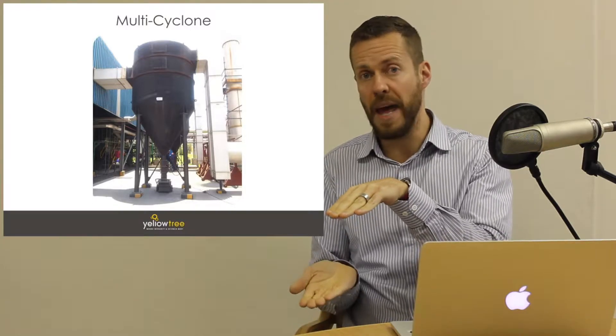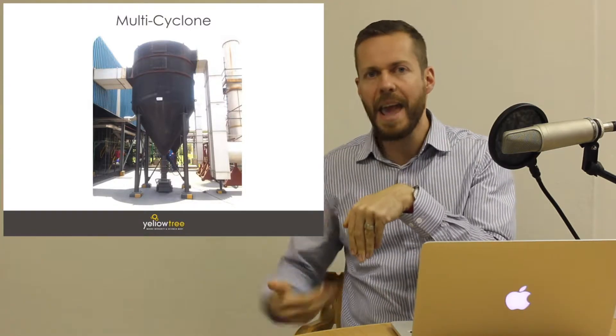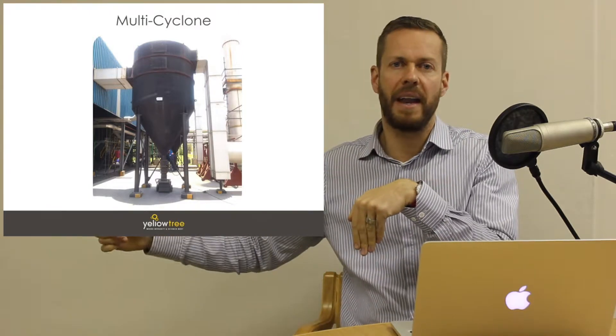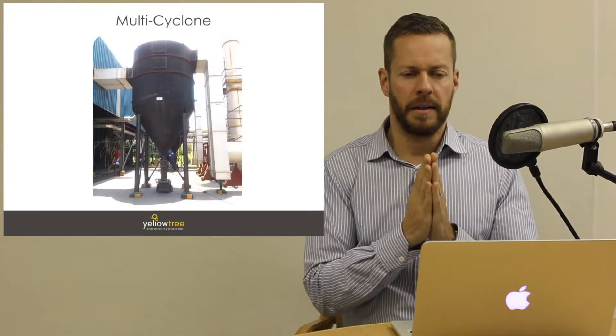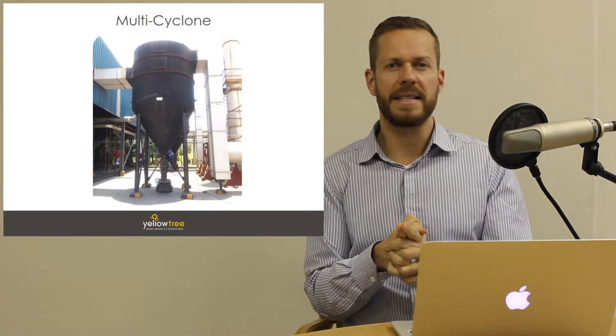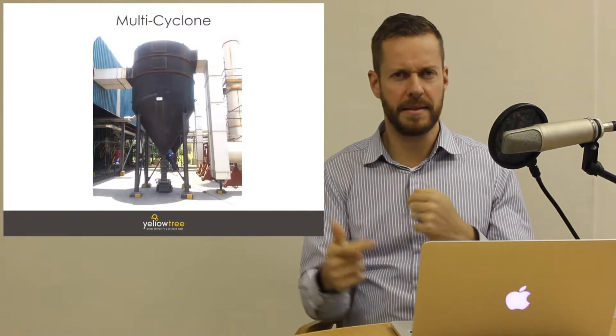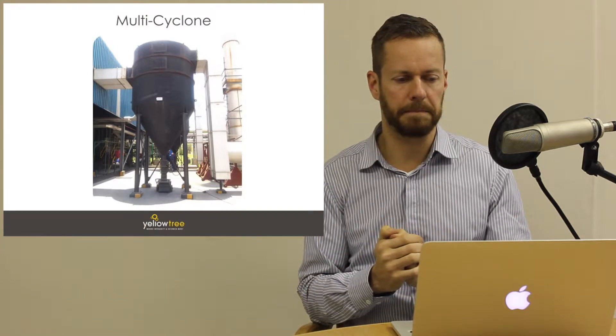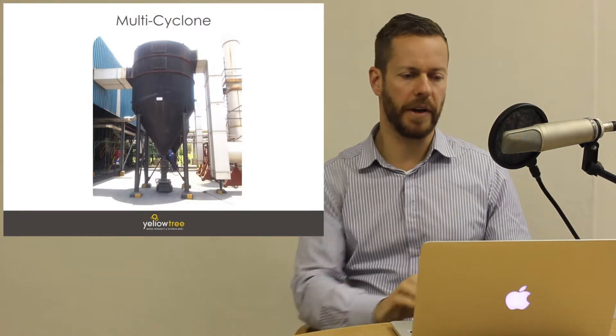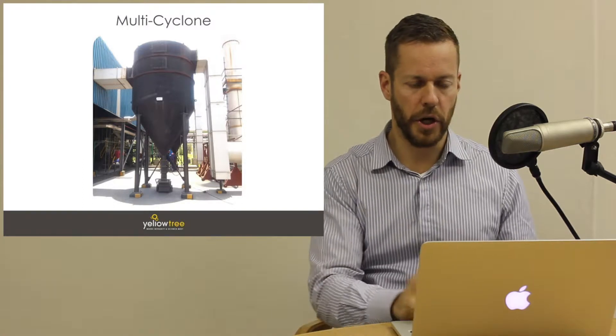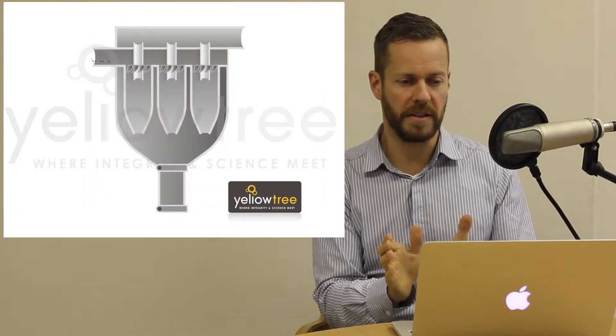If there weren't two flaps — if there was just one and it opened — air would get sucked in because of the ID fan downstream. That's an important concept; if you didn't understand it, please go back and listen again. Now let's take a look at a short video showing the multicyclone we just saw in the previous photograph.